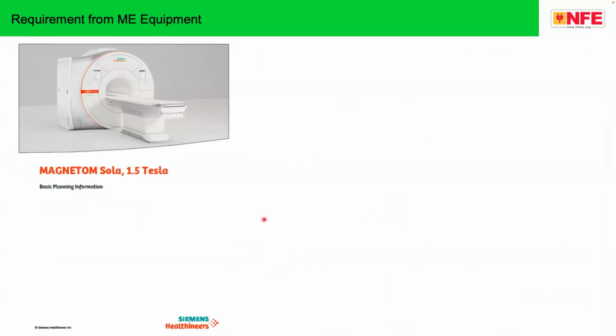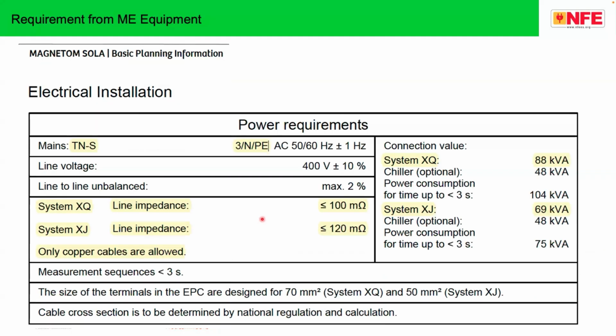Another equipment, as an example, you see Siemens. If you have a manual of this particular machine, you can look into the electrical parameters. It says mains should be TN-S, of course TN-S, very clear. The line impedance shall be less than 100 milliohm.